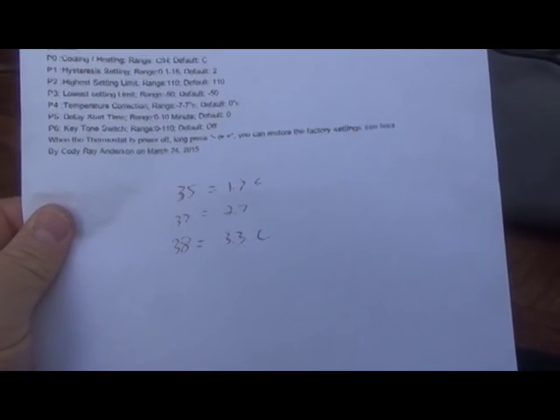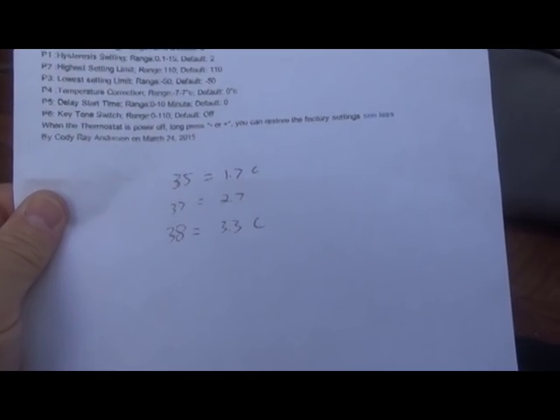37 degrees is 2.7 and 38 degrees is 3.3 Celsius. So what I decided to do is set my parameters for 35 degrees is the target and 37 is the upper limit. So essentially when this thing reaches 2.7 degrees Celsius, it kicks on and it runs until the inside is down to 1.7.